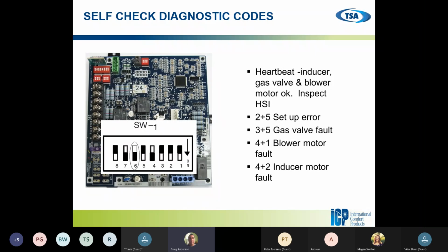So once the sequence is done, on our furnaces with the error light, a steady heartbeat is normal operation. So if it goes through the whole test sequence and we have a steady heartbeat, that's telling us everything I've tested at this point is working properly, so we can go on to the next step. You could get error codes of 2+5, 3+5: gas valve fault, blower motor fault, inducer fault. Those are the kinds of things this test sequence is looking for at the start. And if it doesn't find anything, we're going to stick at a normal heartbeat.